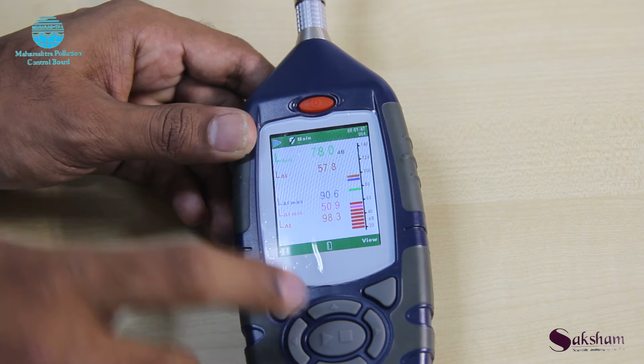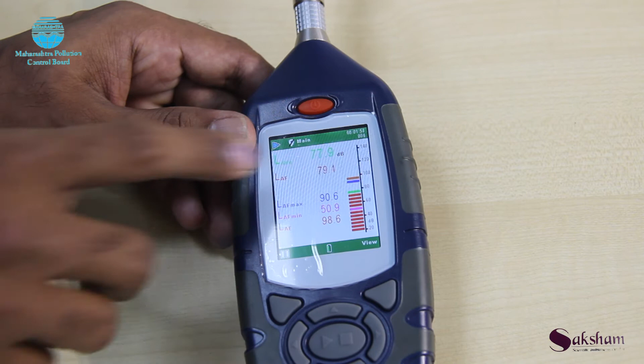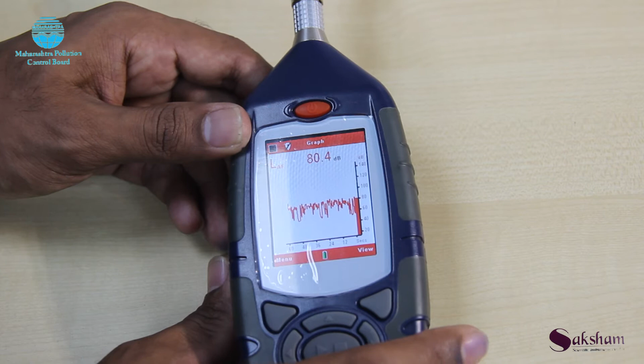On the right hand upper side, if our requirement is to take a reading of 5 minutes, 10 minutes, 1 hour, whatever timing it is showing, after completion of that timing we just press the same button. Again it shows the stop run message. In that time period, whatever peaks are calculated are stored. If you press yes, that reading is stored in this memory, and you will be able to see the LAEQ, LAF max, LAF minimum and LAE. Now whatever reading we have taken is stored in this memory.